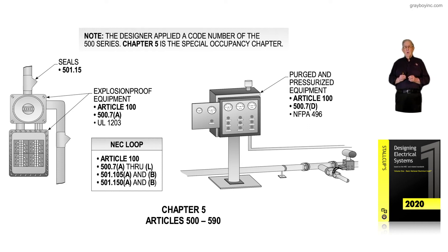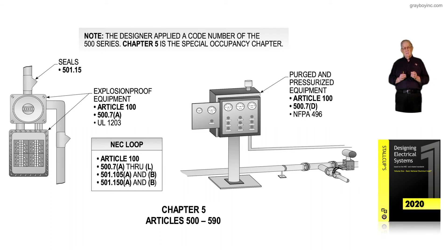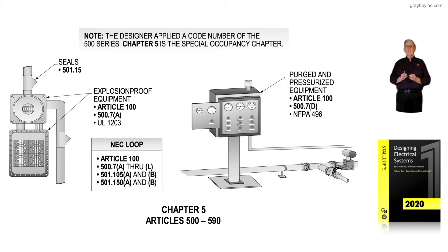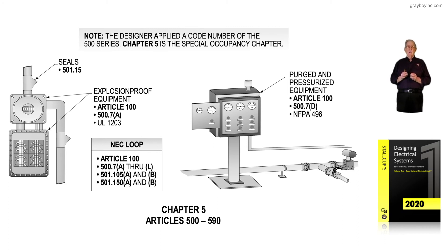For purged and pressurized equipment you also have to use NFPA 496. The speaker chaired that committee for about 12 years. It included NFPA 497, which deals with gases and vapors, and NFPA 499, which deals with dust, flyings, and that kind of thing. NFPA 496 deals with purged and pressurized equipment. The definition of a purged and pressurized system is found in Part 3 of Article 100 in alphabetical order. 500.7D now deals with and allows purged and pressurized equipment to be used.